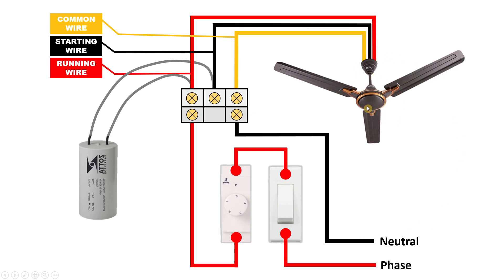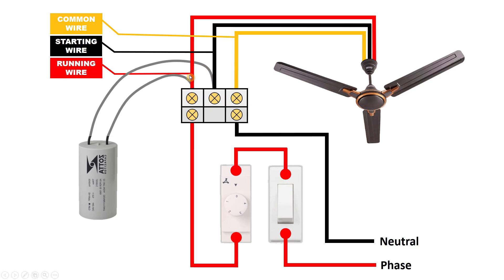Now suppose the direction of the ceiling fan is opposite. To make the direction proper, take the phase supply and connect it to the starting wire terminal instead. Disconnect the red wire from its terminal and connect it to the other terminal, and disconnect the black wire and connect it to the other terminal. We interchange these two wires so that the direction of our ceiling fan changes.